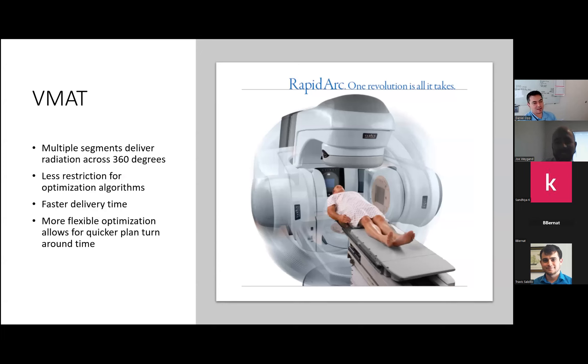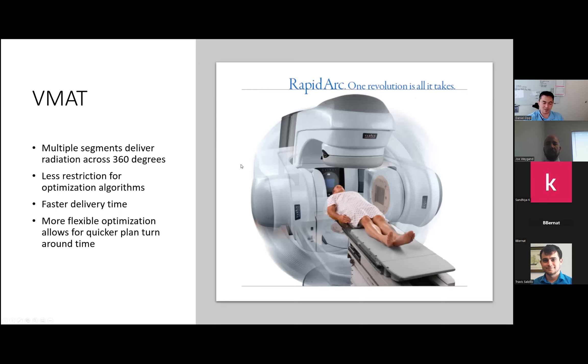The way to improve on IMRT is rotating the gantry all the way through. Varian called it RapidArc; the technical term is VMAT. One revolution was the original claim, but we've gotten to the point where we do at least two arcs, and it's not unusual to see three or four arcs on a plan. VMAT delivers multiple segments across the entire 360-degree rotation around the patient. The exception is for lung plans or anything requiring lateral positioning — there you'd do just a 180-degree arc or a little less.